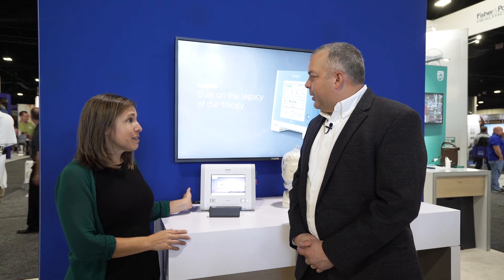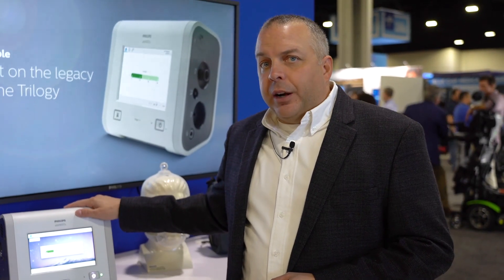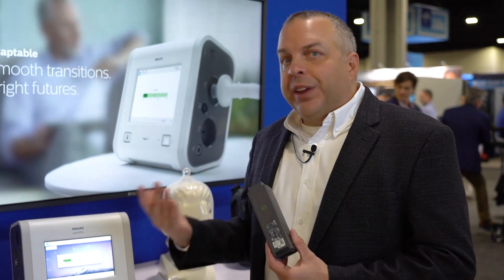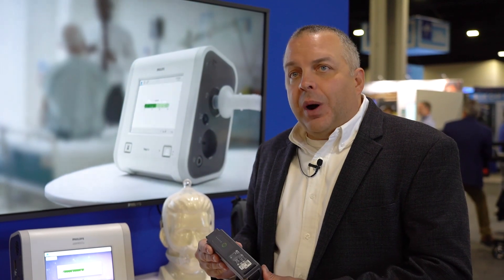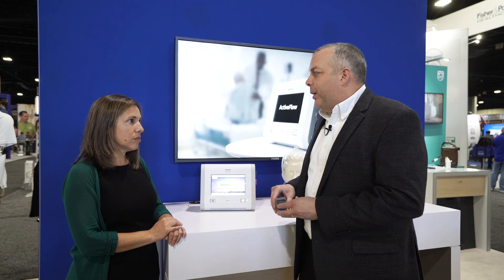That's great. It looks pretty small — is this a portable device? Yes, this is a portable ventilator. It has an internal and also a detachable battery that will allow the patient up to 15 hours outside of the home, which is pivotal when you think about kids going to school or an ALS patient that has to travel great distances to get to their local clinic. It also comes with nice accessories like a bag and wheelchair mounts that will help the patient use the ventilator while on the road.